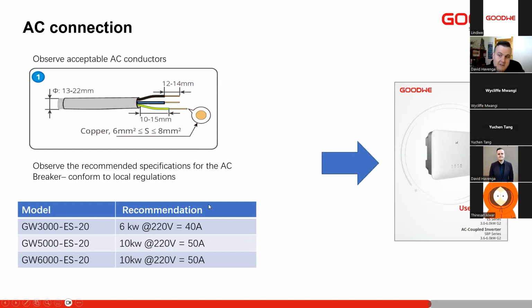Next, we look at breaker sizing. My recommendations for breaker sizing. So due to that overload capability, the maximum consumption from utility, always important to keep these in mind. Very often we install a 3 kilowatt inverter. We might think 3 kilowatts. We only put a 25 amp breaker on it, but it can overload, and customers generally do tend to overload. Always make sure we install the right size cables and the right size breakers. It's never good when we're consuming power from utility that the breaker switches off.